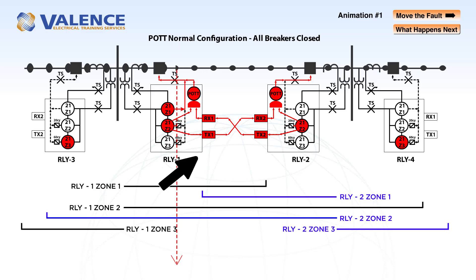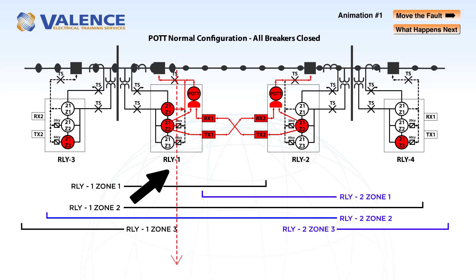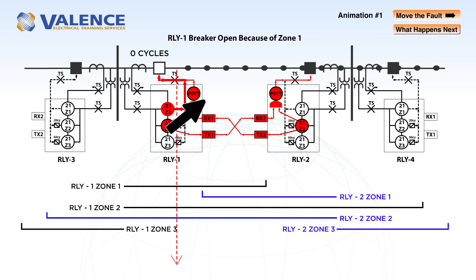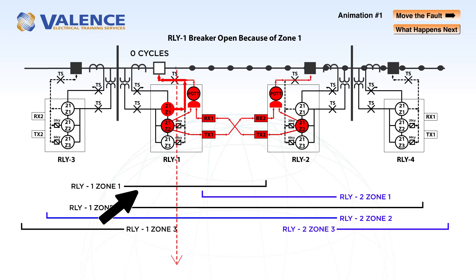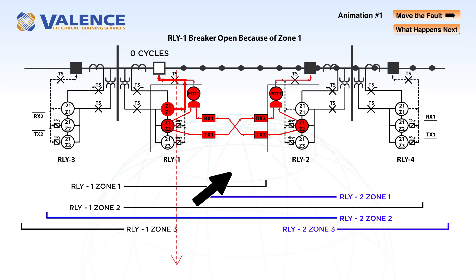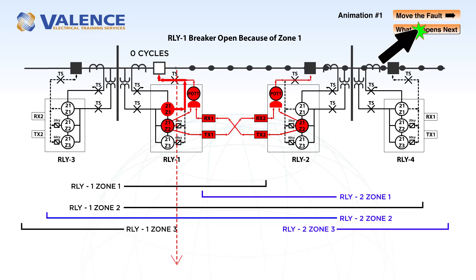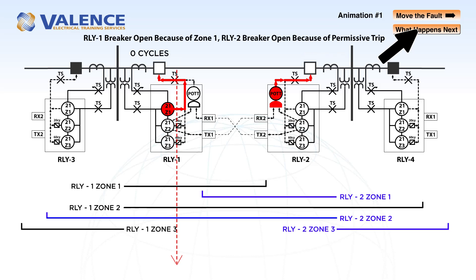In this scenario, relay 1 will still trip instantaneously because of the zone 1 pickup, but relay 2 should operate in less than 6 cycles because both relays detected a zone 2 fault. The 6 cycles could be any small time delay to allow for communication delays.